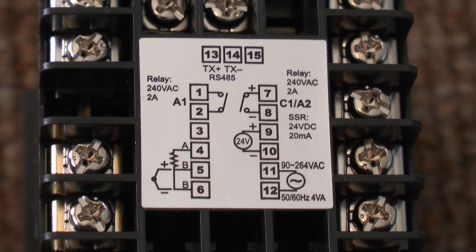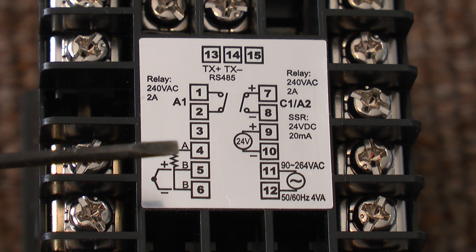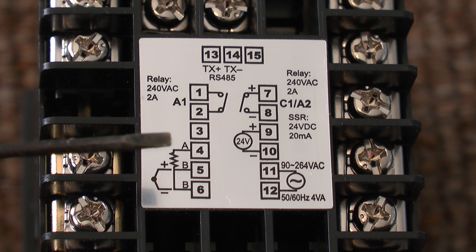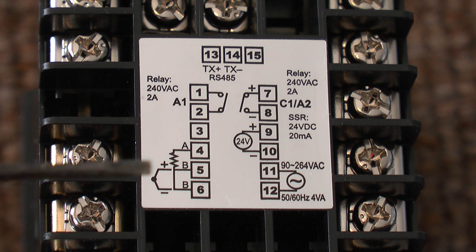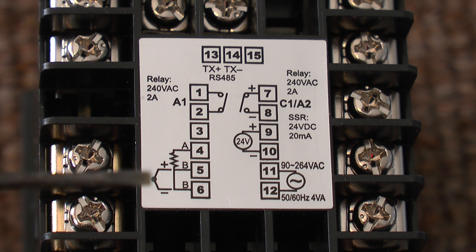If you are using a PT100, it will normally have three wires. One of them will go on terminal 4 and the other two, normally of the same color, will go on terminals 5 and 6.